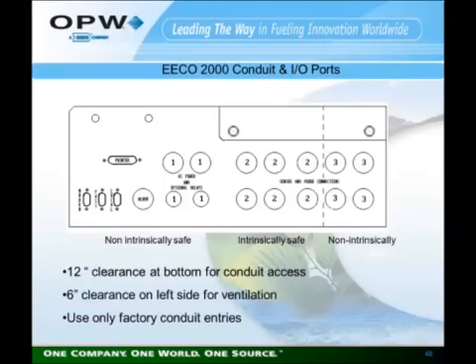Again, we recommend 12-inch clearance on the bottom for conduit access and 6-inch clearance on the left side, not necessarily for communications access on this unit, but for ventilation. And as on the 1500, you're to use only the factory conduit entries. Any other holes drilled in the unit will void any remaining warranty.